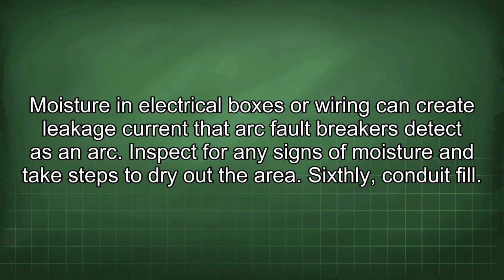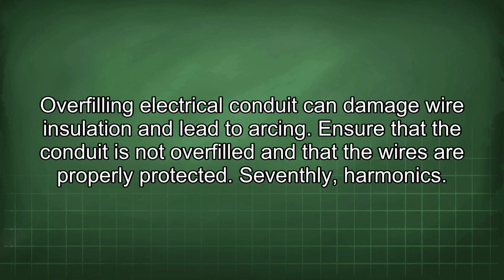Inspect for any signs of moisture and take steps to dry out the area. Sixthly, conduit fill. Overfilling electrical conduit can damage wire insulation and lead to arcing. Ensure that the conduit is not overfilled and that the wires are properly protected.